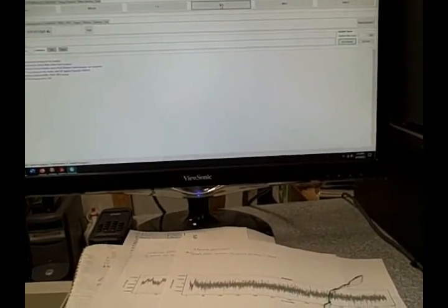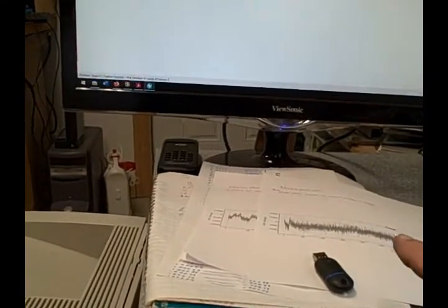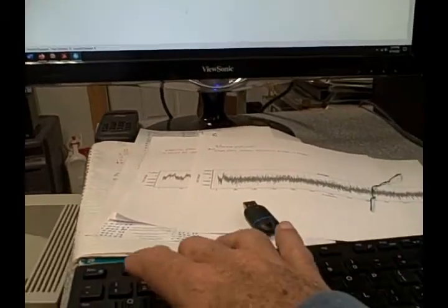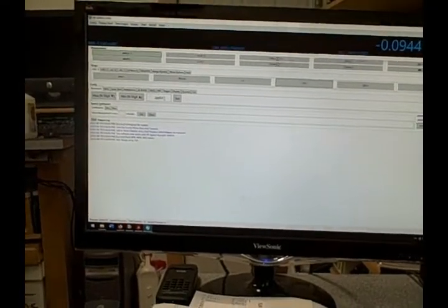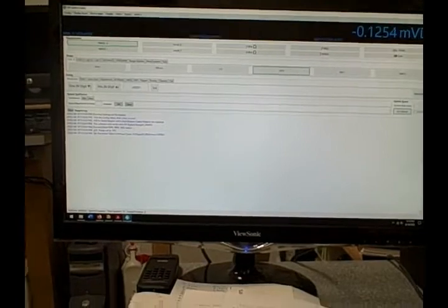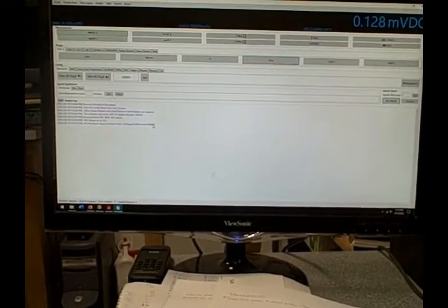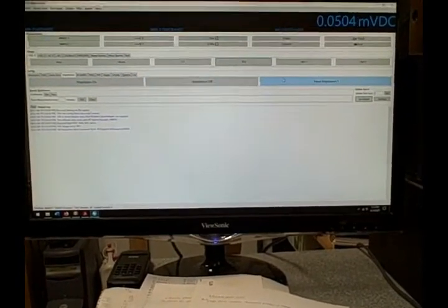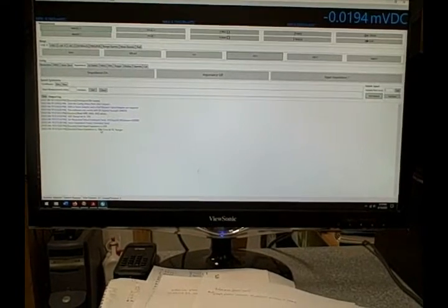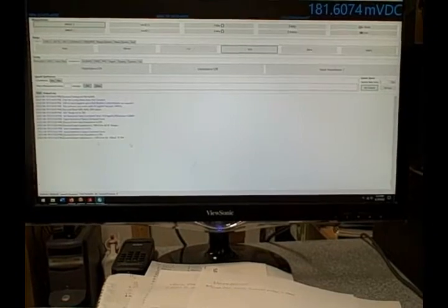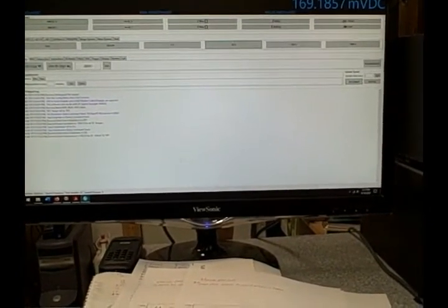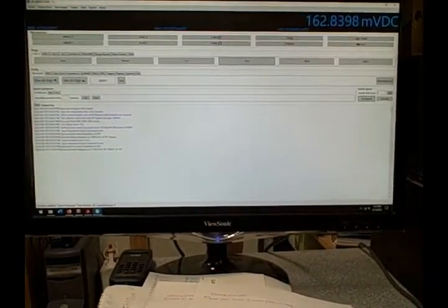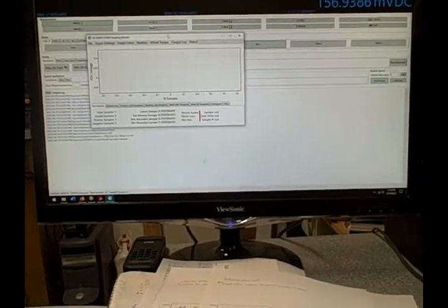I can put myself in a manual range if I want. I can slip in a resolution. So I'm saying 0.00001. So I want to be within 10 microvolts of resolution. I'm going to set that. It confirmed that I set my range to 10 volts. It confirmed that I set my resolution the way I want. I want my impedance to be higher than 10 meg. I want to go to 10 gig. Right now I put impedance on. And I can confirm that it now is switched to 10 gigs. Which it is. So we're good. And now I'm going to bring up graphs up at the top. And I'm saying show the graph. Here it's bringing graph up.